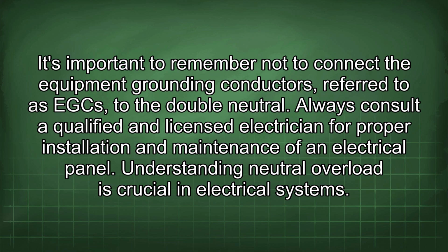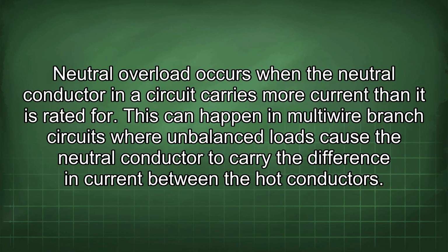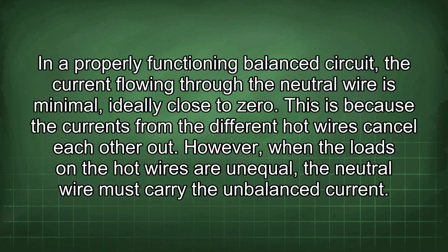Understanding neutral overload is crucial in electrical systems. Neutral overload occurs when the neutral conductor in a circuit carries more current than it is rated for. This can happen in multi-wire branch circuits where imbalanced loads cause the neutral conductor to carry the difference in current between the hot conductors. In a properly functioning balanced circuit, the current flowing through the neutral wire is minimal, ideally close to zero. This is because the currents from the different hot wires cancel each other out. However, when the loads on the hot wires are unequal, the neutral wire must carry the unbalanced current.